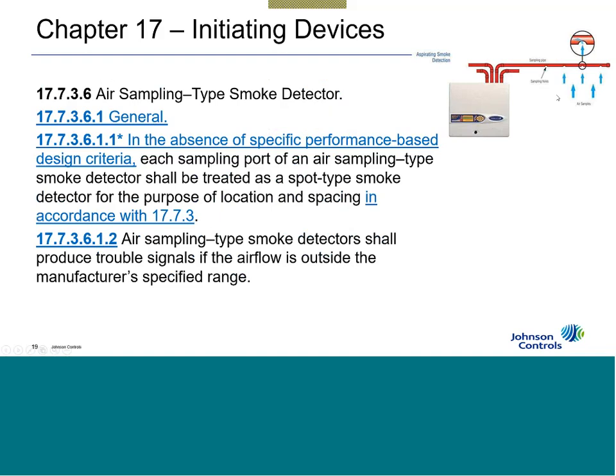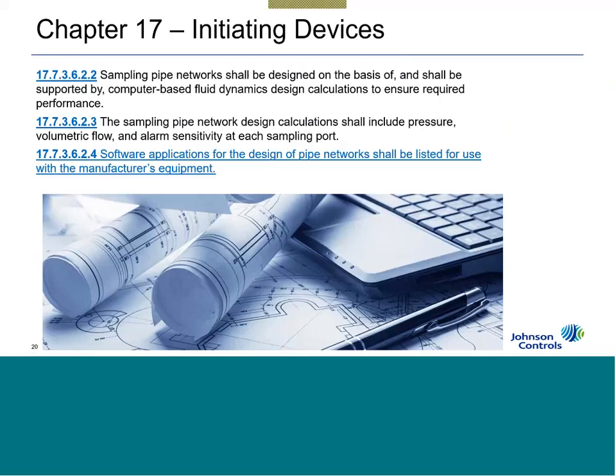If you use, for example, Vesda. Vesda is a big partner with Johnson Controls. There is Vesda's software that you use to design the system. How big is my area? How high is the floor? And it will tell you the size of the tubing, how far apart the holes go, the size of the holes, the end cap that you use, the speed of the fan. Everything is calculated out. So what this section is telling you is if you don't have that performance-based design criteria, every port needs to be treated like a spot-type detector and spaced like a spot-type detector.